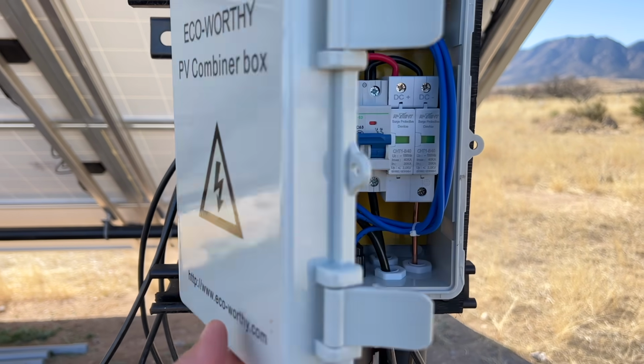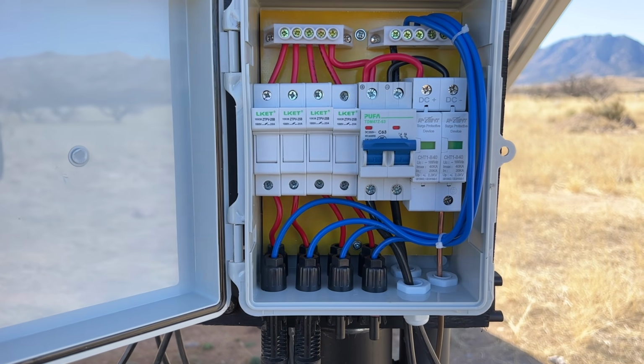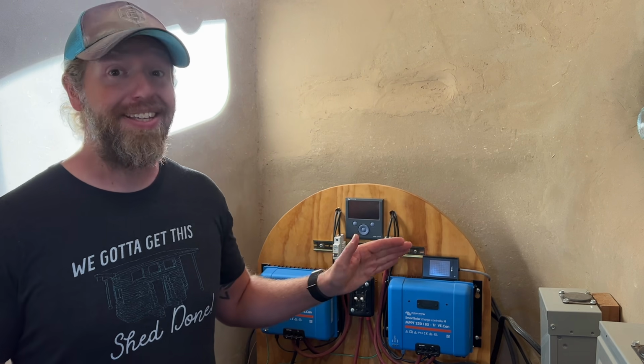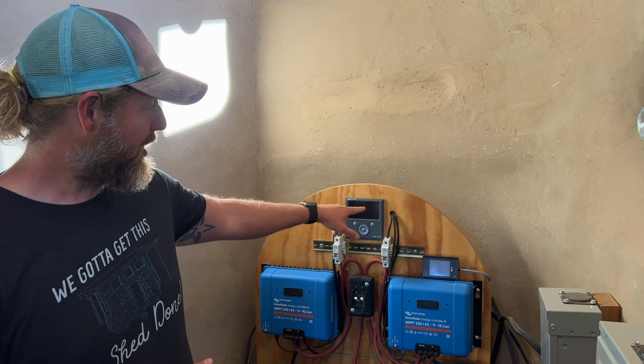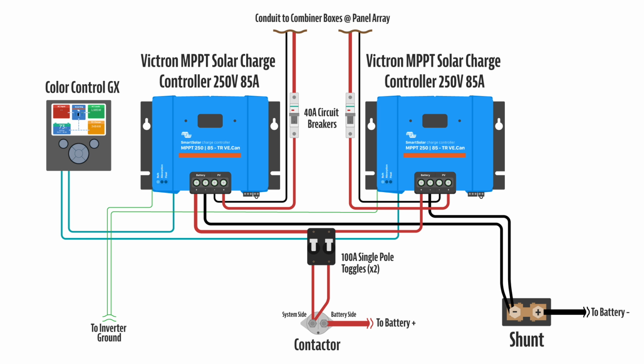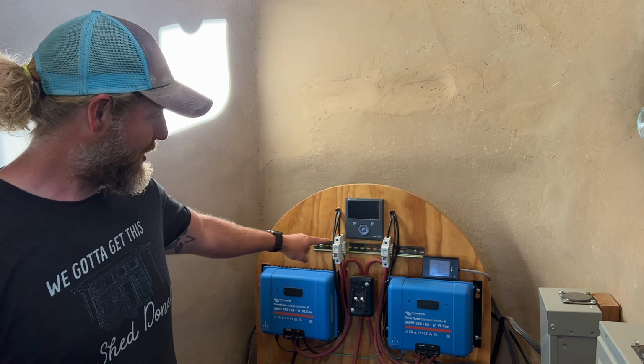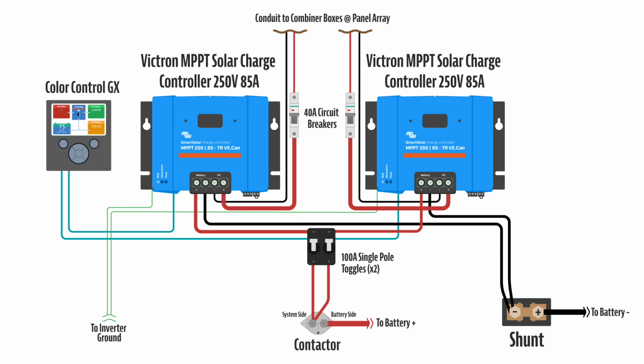Even though we have the combiner boxes back at the solar panel array with their own circuit breakers, we've added a second set of circuit breakers right here coming in, from the positive lines on each combiner box array. From there, we ran 2-gauge cable from the circuit breaker into the positive PV of each one, while the negative lines still came through directly to the negative PV.